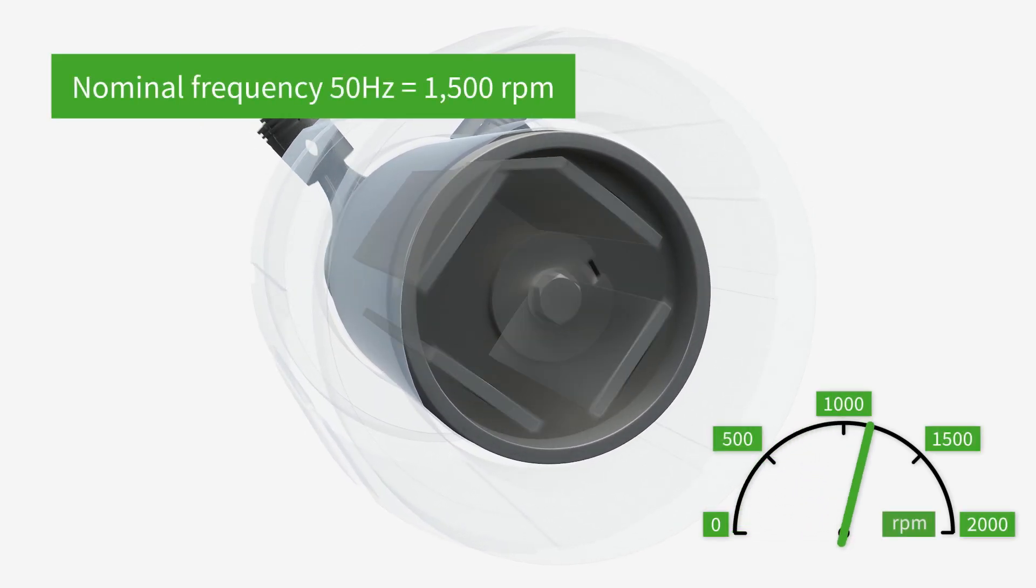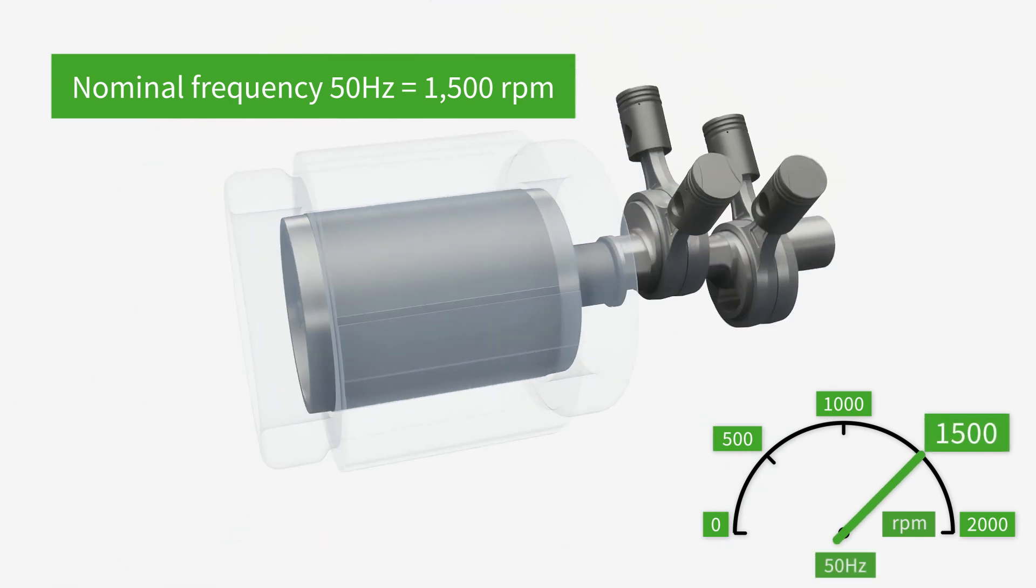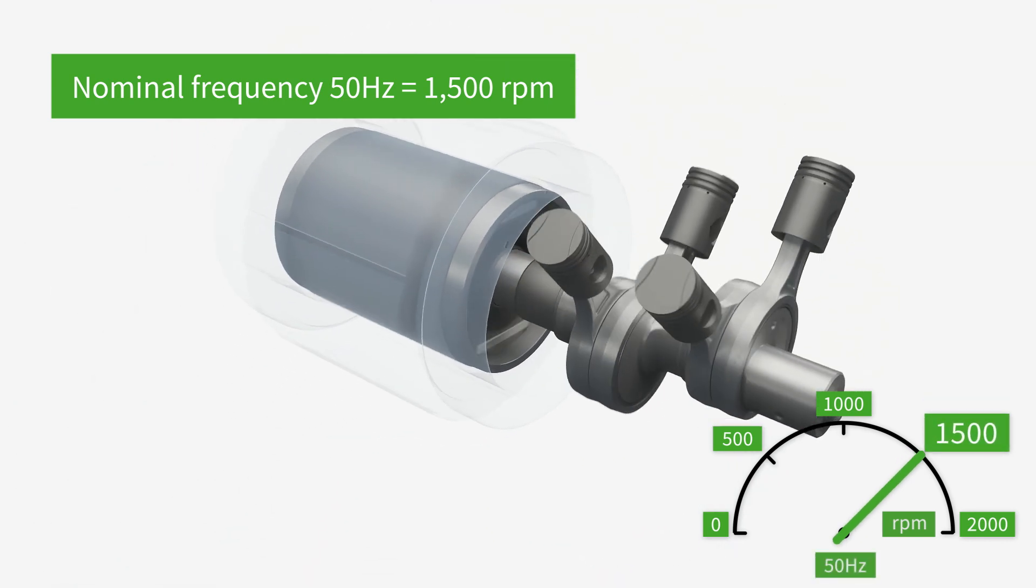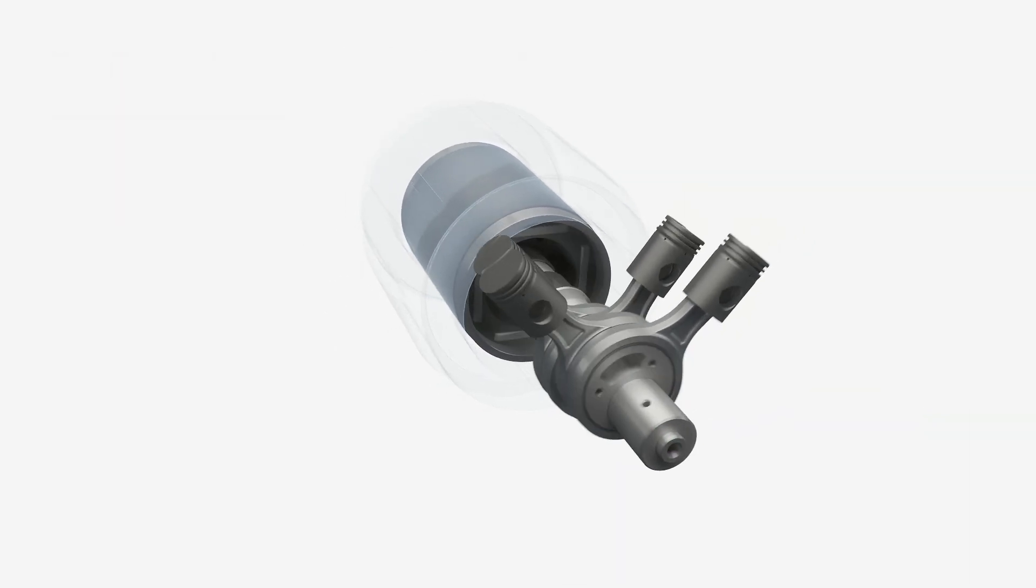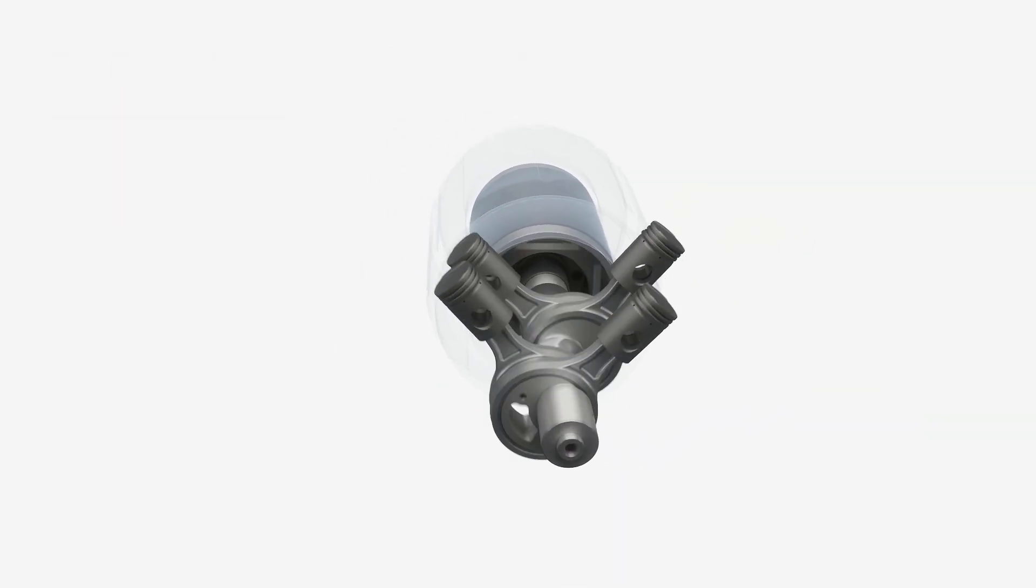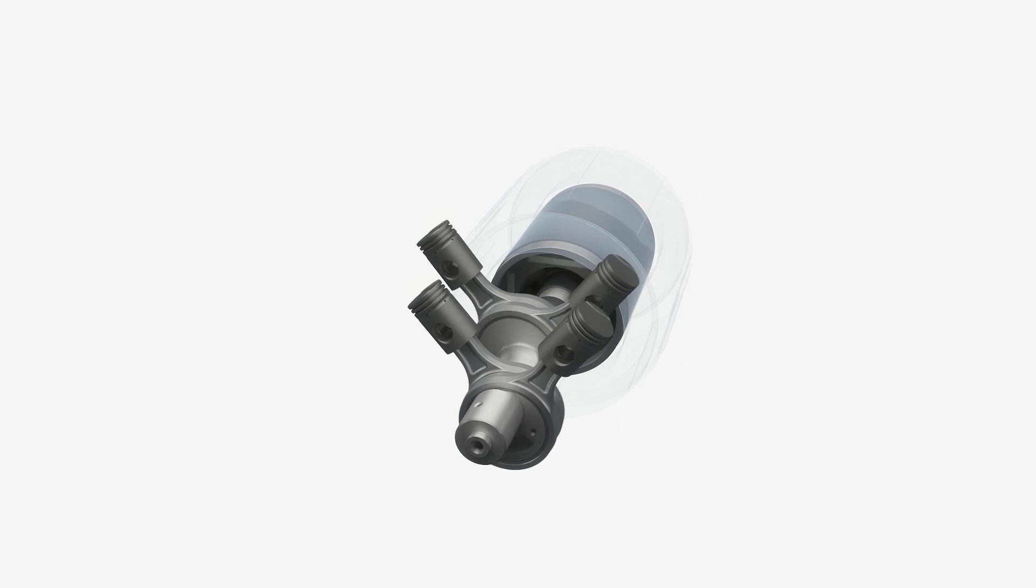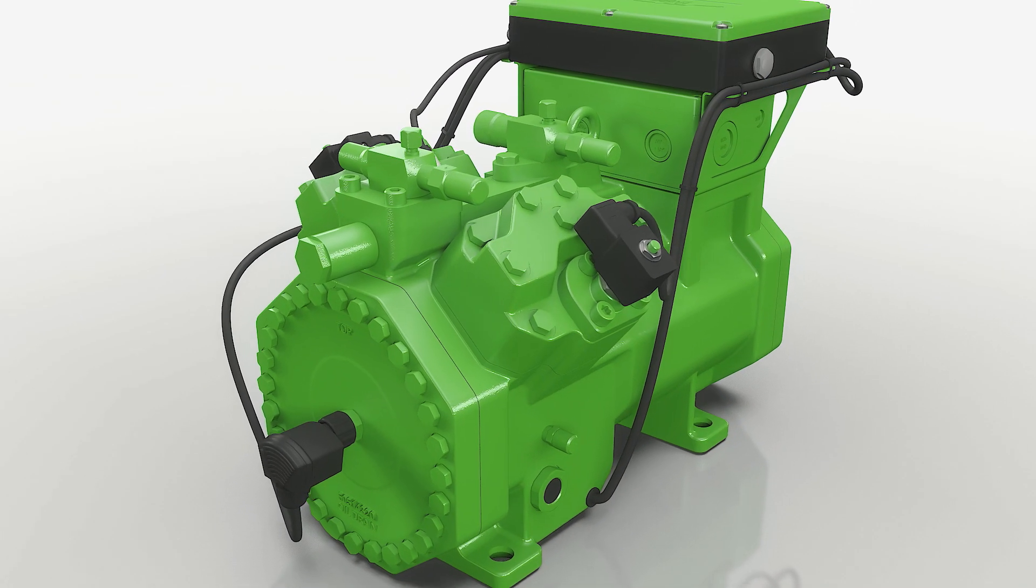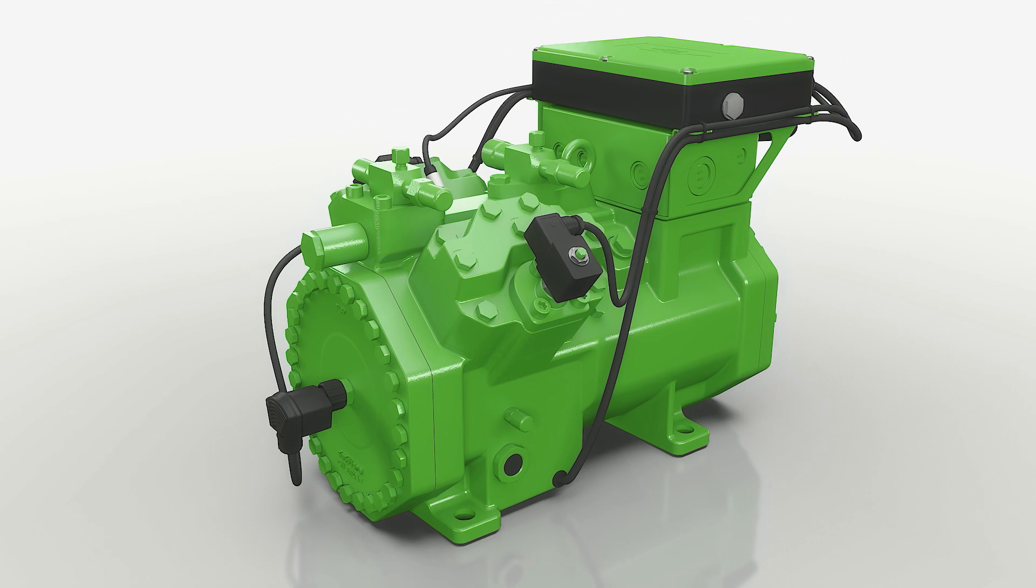After its asynchronous start, the motor synchronizes with the supply frequency and ultimately runs in synchronous operation. The LSPM technology combines the high efficiency of a synchronous motor with the robust design and ease of use of an asynchronous motor.